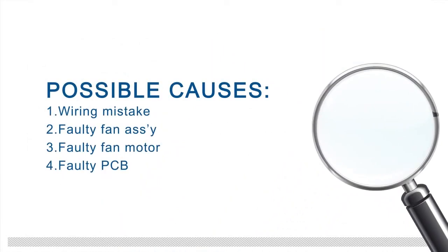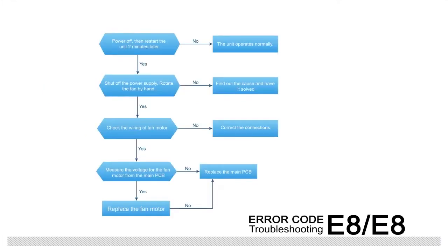This failure may be caused by wiring mistake, faulty fan assembly, faulty fan motor, and faulty PCB. Troubleshooting is shown in the figure.